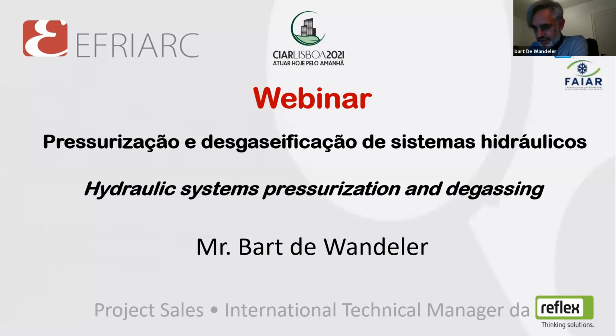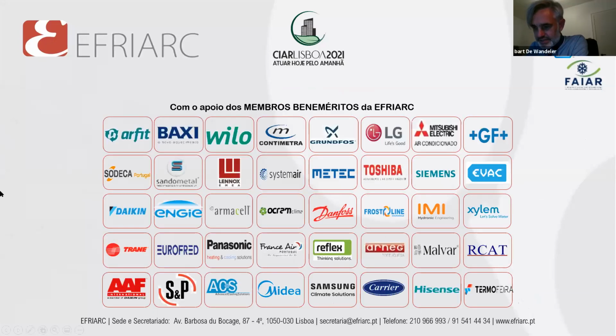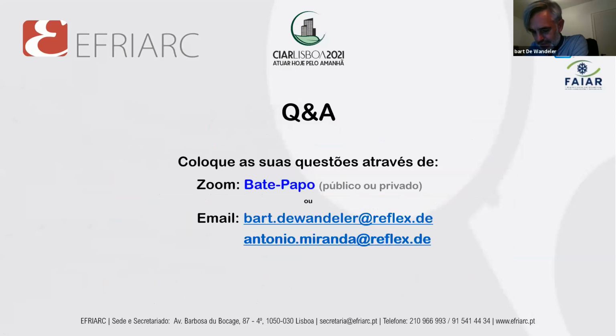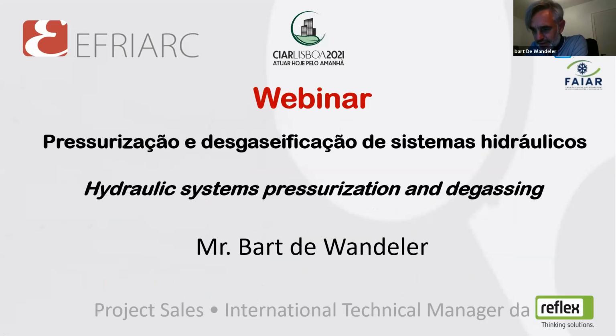Yeah, first of all, the most important thing to start with is the expansion tank. I see those boilers often have their own small tank, usually 4 to 6 liters expansion. In my opinion this is okay because those apartments don't have a lot of water content, but the visible aspect is that those small expansion tanks may not work as well as having an extra small expansion tank - I mean 10, 8 or 12 liters - where you can put a bit more water reserve. The problem is also that in those boiler rooms with small expansion tanks, it's difficult to see when they are broken, and if the P0 is already too high, that's the end of the story.